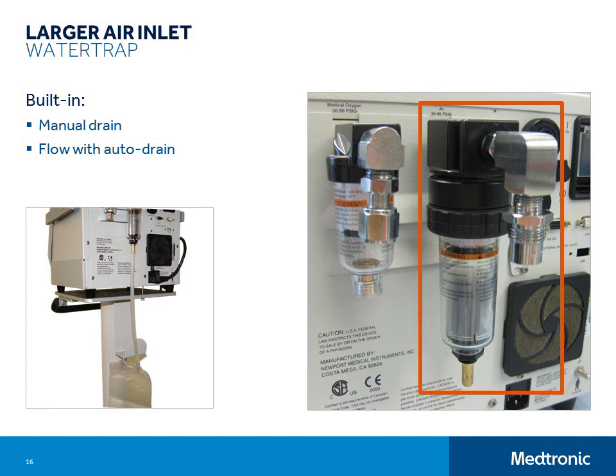To do this, just push up on the large pin at the bottom of the jar assembly while holding a receptacle under the trap, or attach suction tubing from a bedside vacuum canister to the large pin on the bottom of the jar assembly and then push up on it. For your convenience, we also offer an optional drain kit which contains drain tubing and a drain bag, so that the water that drains during the auto drain function, or water that you manually drain from the system, is captured in the bag.